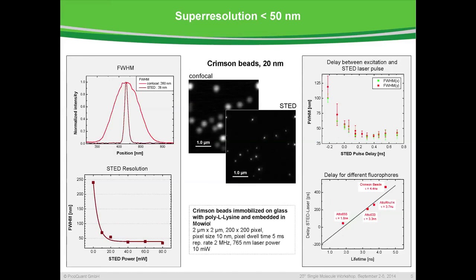I'd like to continue with some proof-of-principle measurements. First we look at small fluorescent beads — crimson beads, 20 nanometers in diameter — and look at the confocal and the STED image, which shows much enhanced resolution. If you look at the cross-section of a single bead, we see more or less diffraction-limited resolution at 260 nanometers, whereas in the STED image we have a very sharp peak of 28 nanometers. The resolution of the STED microscope is strongly coupled with the STED power that we use.